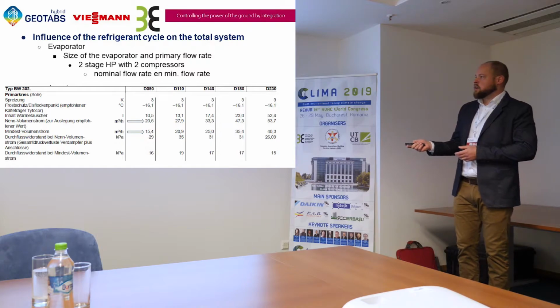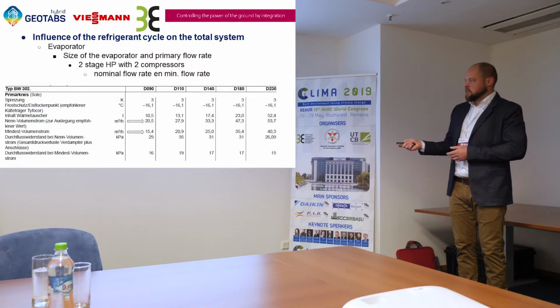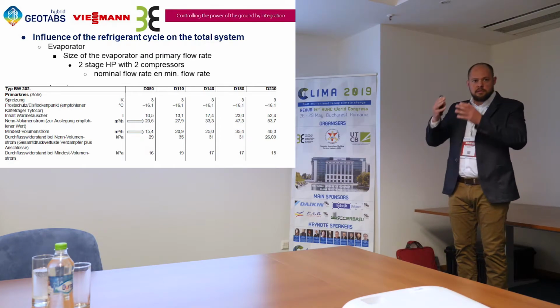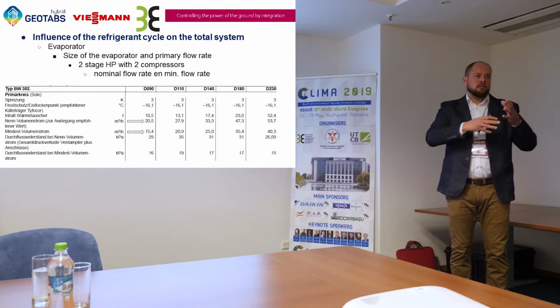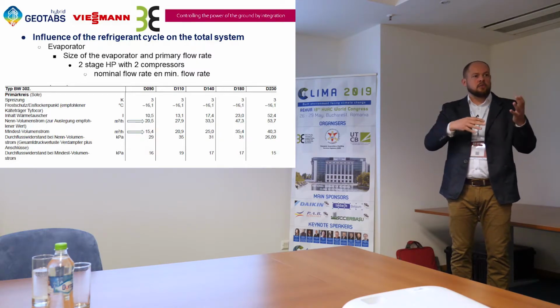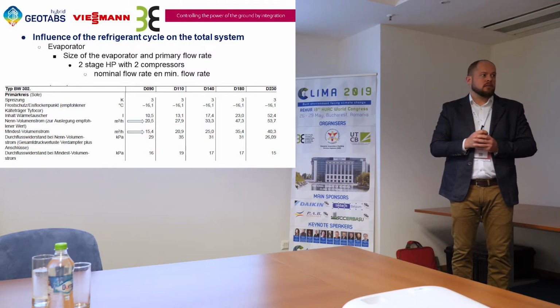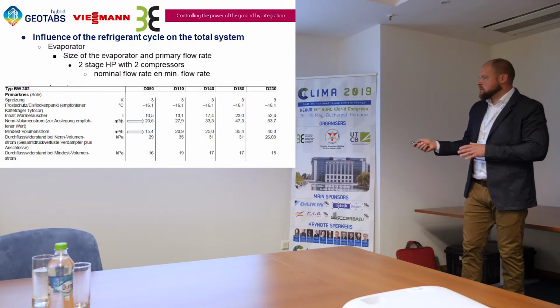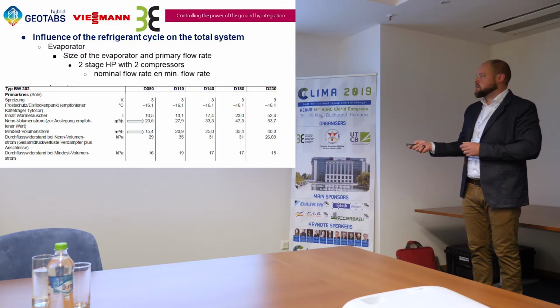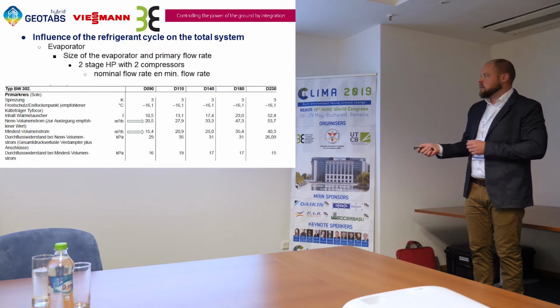So you can see here, we have to calculate the flow rate. You have a nominal flow rate of about 20 cubic meters per hour in this example, but the minimum flow rate is not half of this. So it's not because the heat pump switches to maximum power and half the power that the flow rate is going down by half. That's very important. It's about 75% of the initial flow rate that you can see here. That's the minimum flow rate, and why that is I will show you in the second slide.